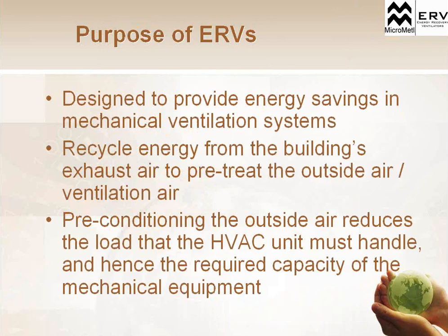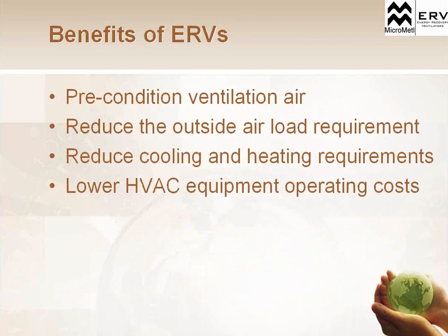So what's the purpose of an ERV? Basically, an ERV is designed to provide energy savings in a mechanical ventilation system. So anywhere where we're using a large amount of ventilation air, this energy recovery unit is going to recycle energy that we've already paid for the building to heat or cool. So we're going to use the energy from exhausted air, and we're going to capture that and preheat or pre-cool the outside ventilation air that we're bringing in. So essentially, we're preconditioning the outside air using the energy that we've already paid to heat and cool the air inside the building with. That sounds a bit confusing, so we'll break it down one more time.